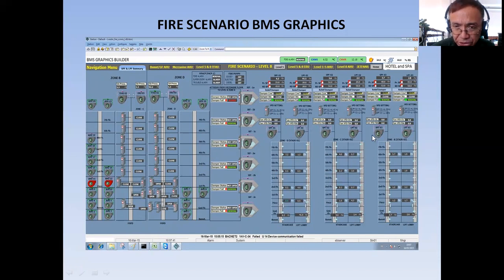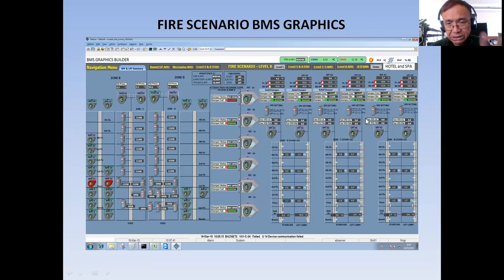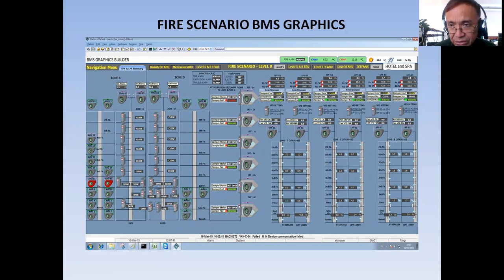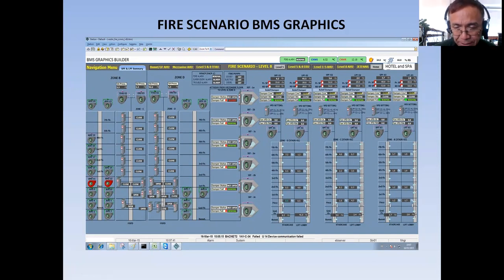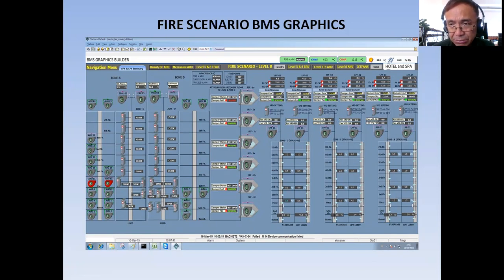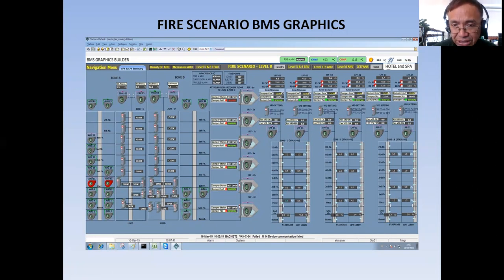I'm also showing the actual pressure readings. There is no fire scenario here — I just screen-captured this graphics to use it later in my tutorial. I also have the status of the relief dampers. This relief damper is the one releasing the excess pressure in the lift lobby or in the staircase, because if the pressure is too much, nobody will be able to enter the said area when there is fire. So the pressure should be maintained properly.